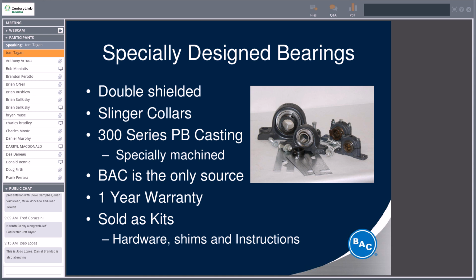The bearings are specially designed for the cooling tower industry. As I mentioned earlier, the cooling tower is the world's greatest air scrubber, but it's also a pretty violent environment, almost a hurricane effect inside of it. You've got high winds and you're introducing water to high winds. So the motors and the bearings and the bushings and everything need to be top grade in order to withstand that type of environment.